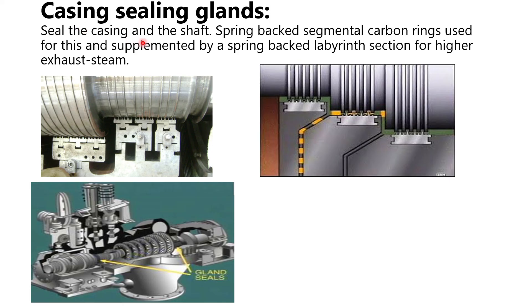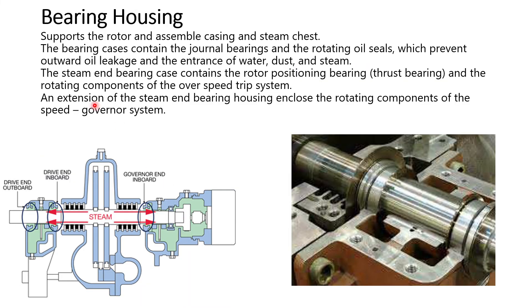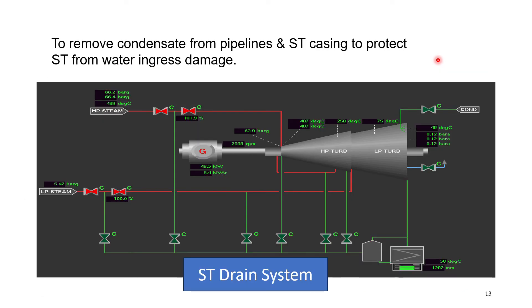In this figure you can see various arrangements of the seal casing, shaft, carbon ring seal, and labyrinth shaft seal. At the bottom of the drawing you can see the location of the gland seal. The bearing housing supports the rotor and assembles the casing and steam chest. The bearing housing contains the gland bearing to prevent seal leakages, and houses both thrust and radial bearings. It also houses the over-speed tripping mechanism. Steam traps with free drains are provided at various locations to remove condensate and prevent damage from it.